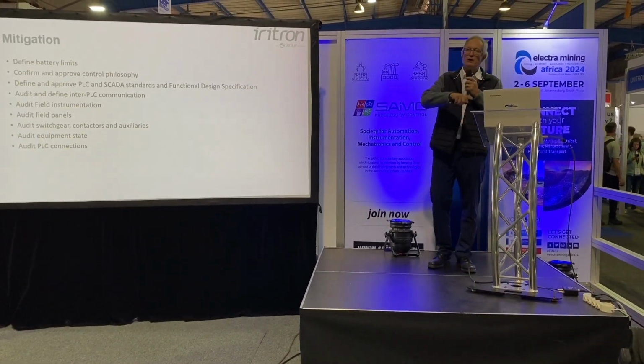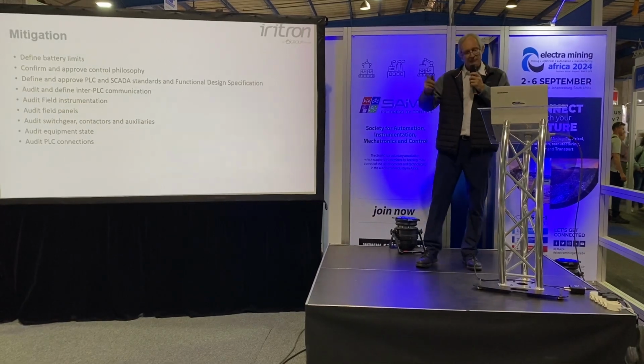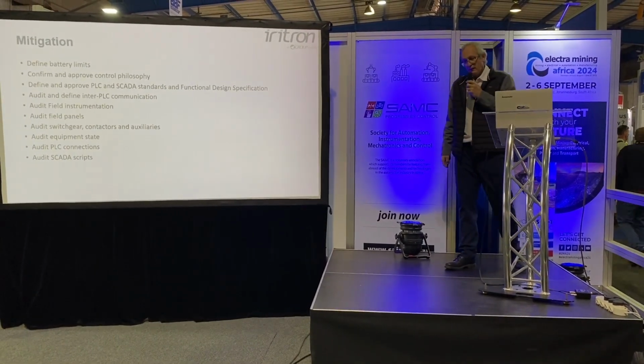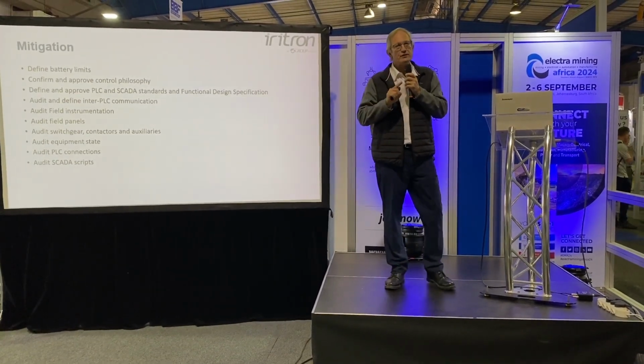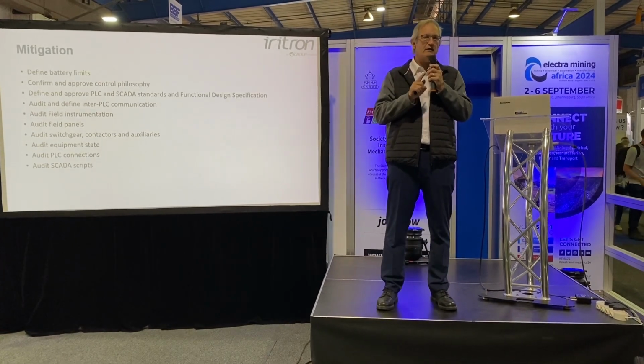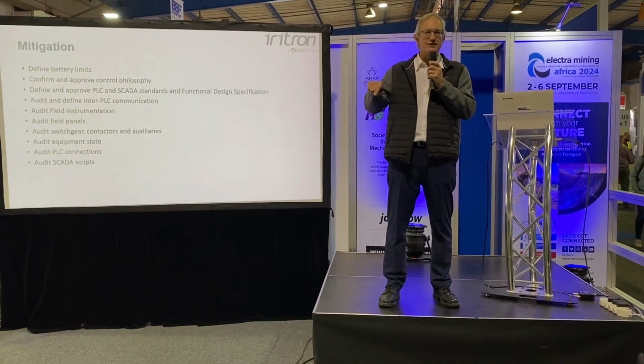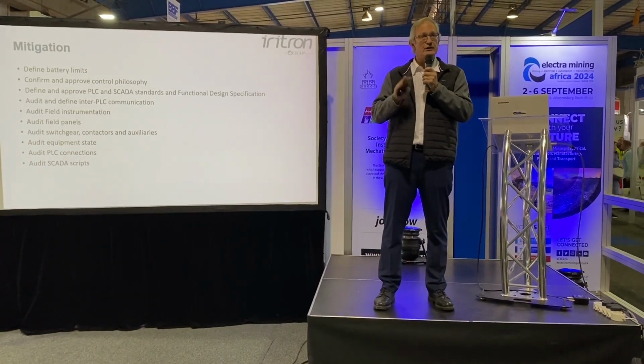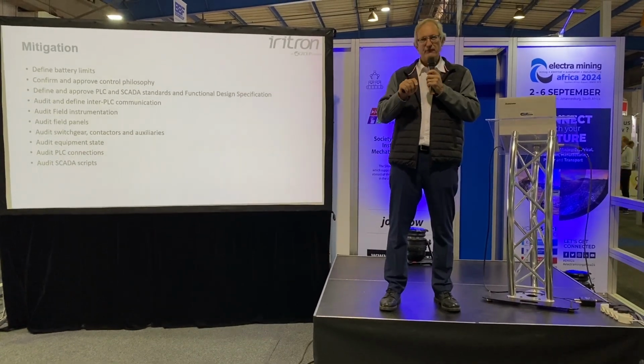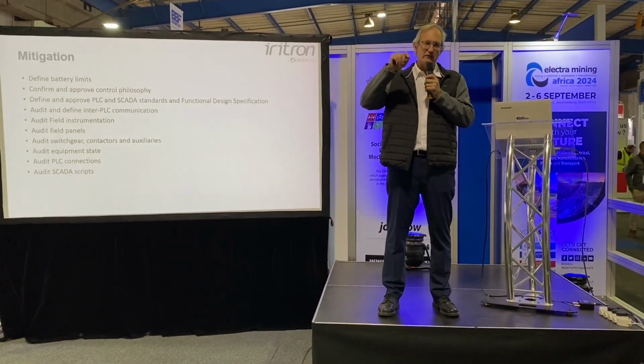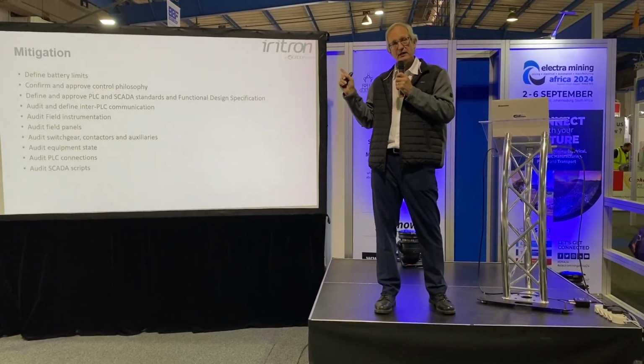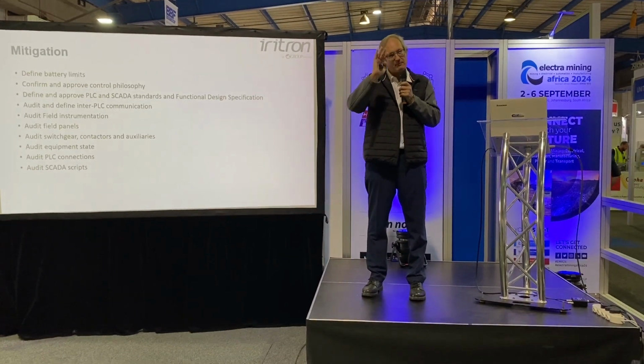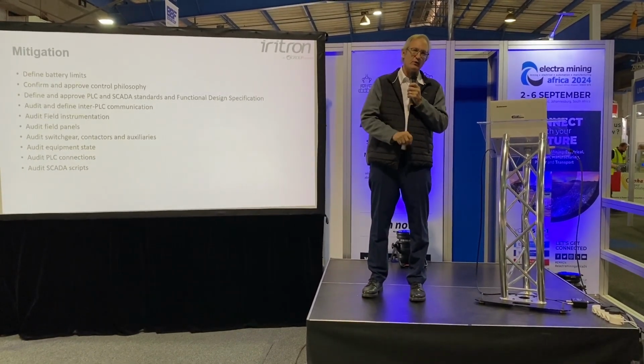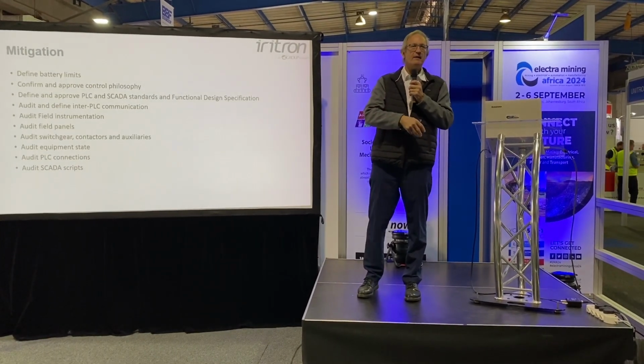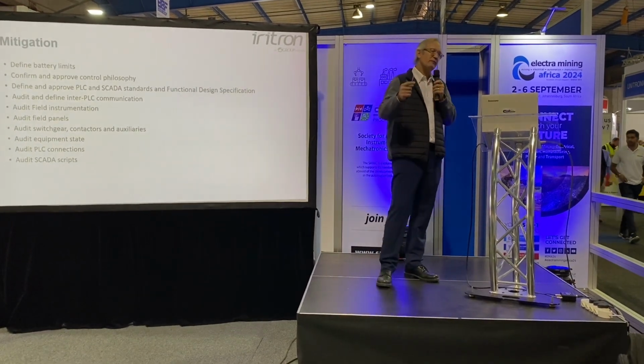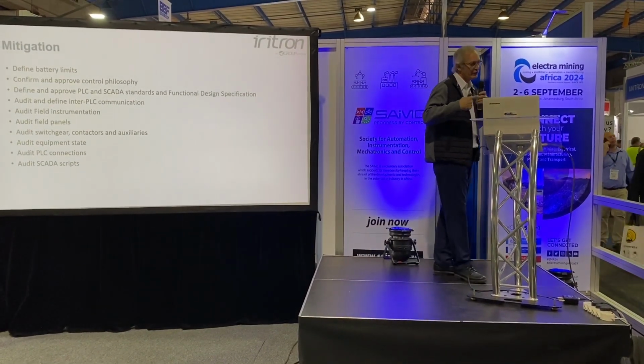PLC connections: also ensure that the PLC connections are all sound, comms are happening between them. SCADA scripts. Now that's an interesting thing because people don't necessarily think or assume that control will be done in the SCADA, because it is not best practice and it is not standard. However, you will find that there's stuff in the SCADA that directly controls the plant. So you need to go and identify and find out those scripts. Go through each one of the pages. See how they work. See how the animation works. See how the control and the comms work. Make sure that there's no scripts in there that will basically be a hurdle when you do commission.